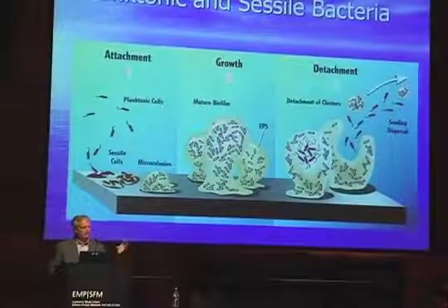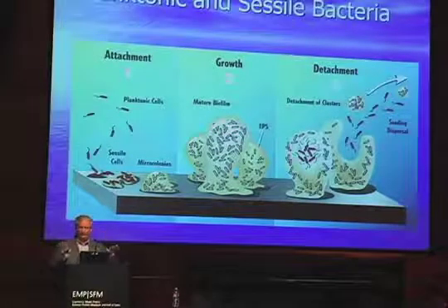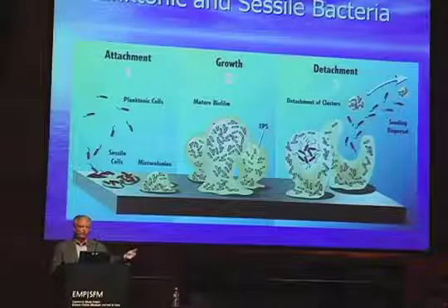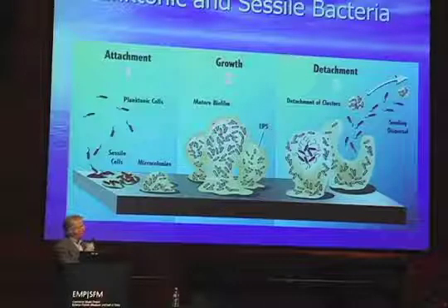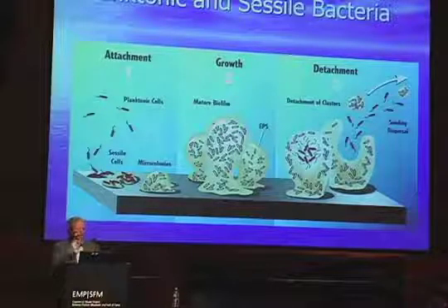So most people that do the bacteria dip slides on the water, they say, oh, my bacteria is good, things are perfect, life's good, but they wonder why they're seeing corrosion on their coupons or seeing corrosion in the system. It's because they're not dealing with the sessile bacteria on there. And we'll talk about biocide programs in a little bit.